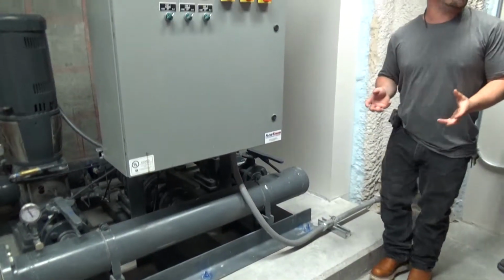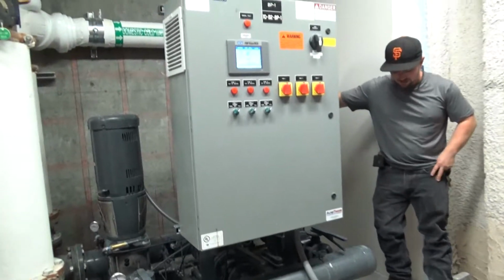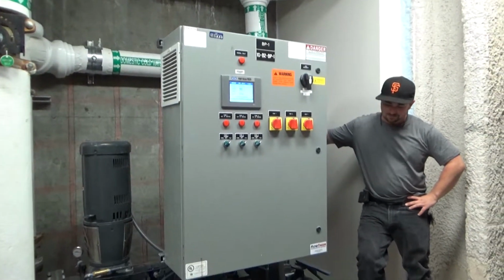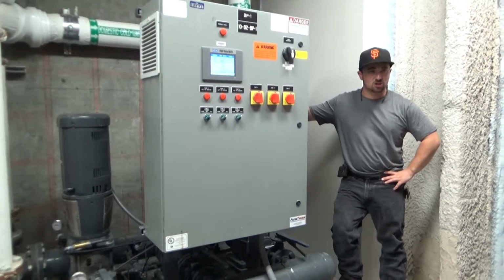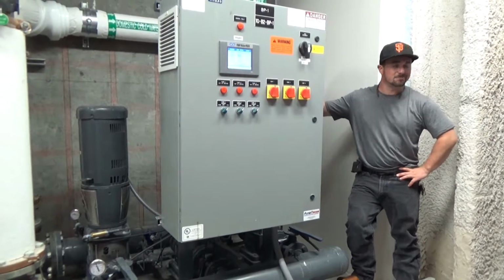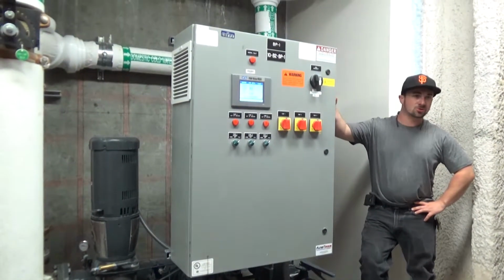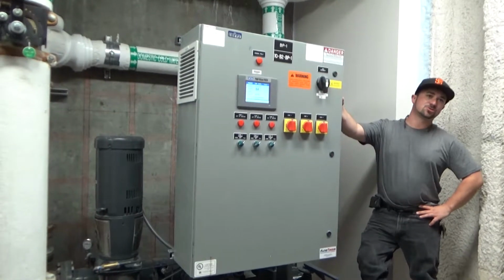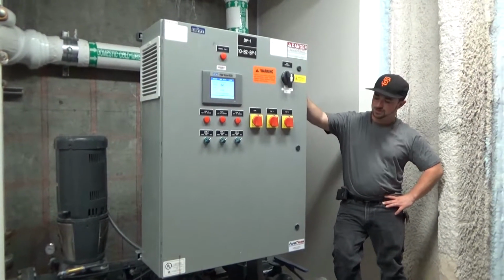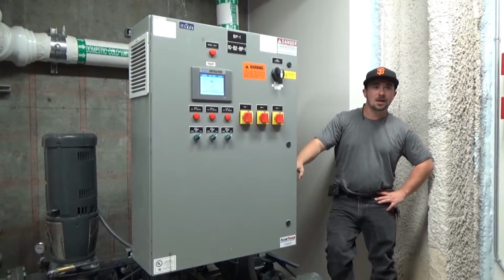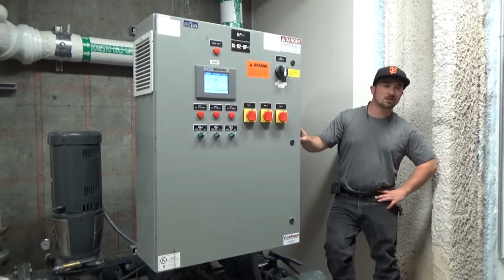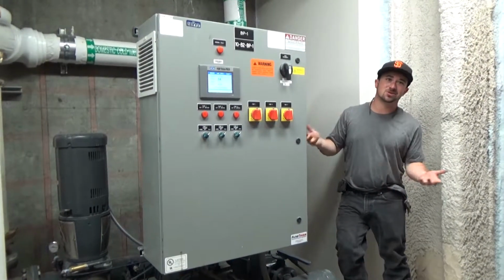So every once in a while, especially after construction happened, it might be a good thing to pull that filter out and maybe replace it in a couple months. Every time after construction, you get construction dust and it fills up, and you don't want to restrict flow through here because then you start overheating these electrical components and it's downhill from there. So, do you know offhand what size that filter is? I don't off the top of my head. Every panel's different. All our different panel sizes, so they're all kind of custom.